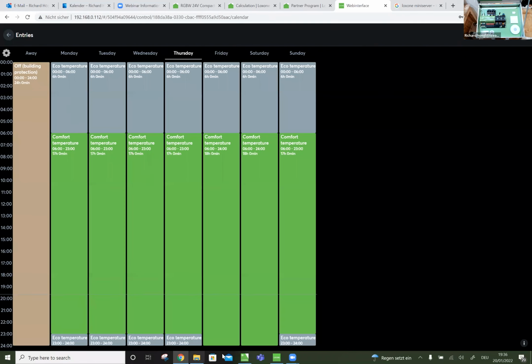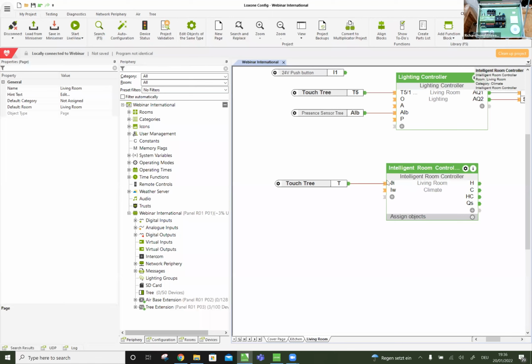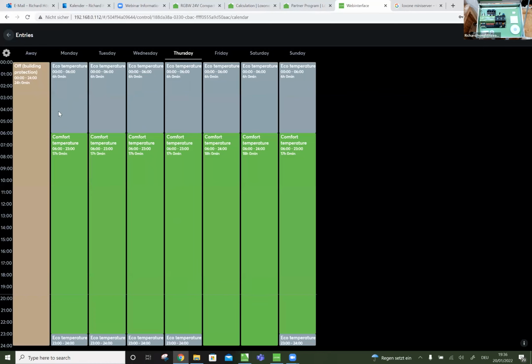What we have integrated in this function block is a learning of the room's behavior. The first day after installation, the function block doesn't know, so it just starts a couple of hours before. It will notice, oh, I started at 2 but reached the temperature already at 4. So the next day it starts later, until it learns exactly how long it takes to get the room to the desired temperature. The customer only needs to say when they want it, not calculate that they have to start heating at 3 a.m. It learns the room's behavior instead.